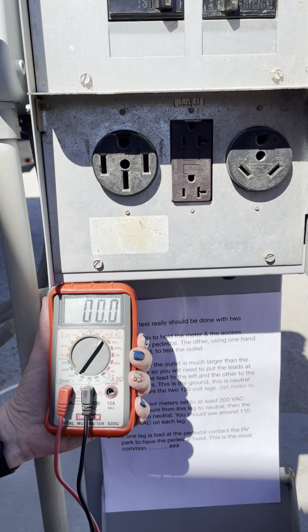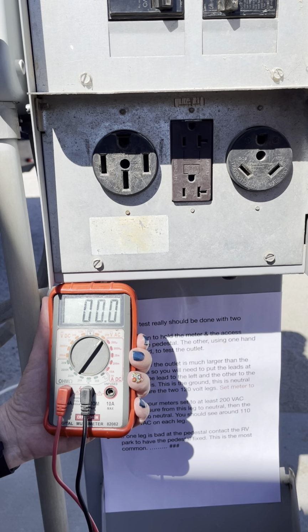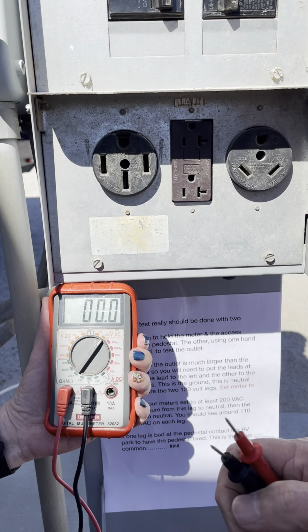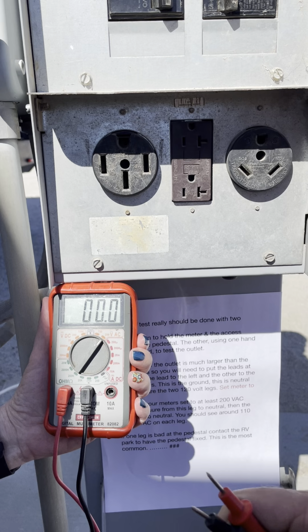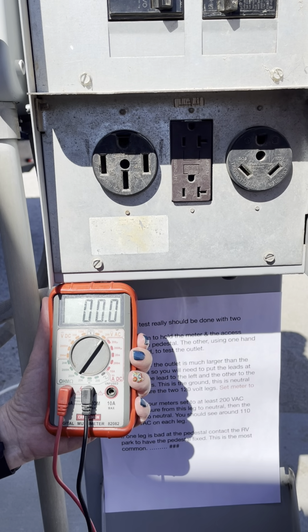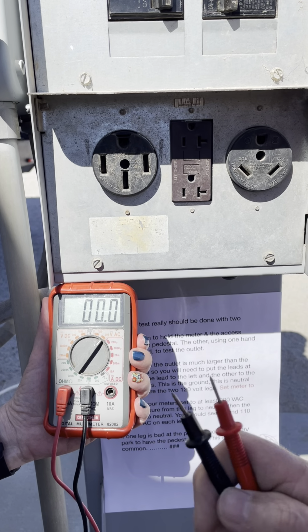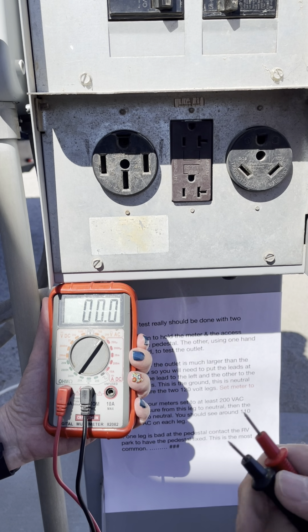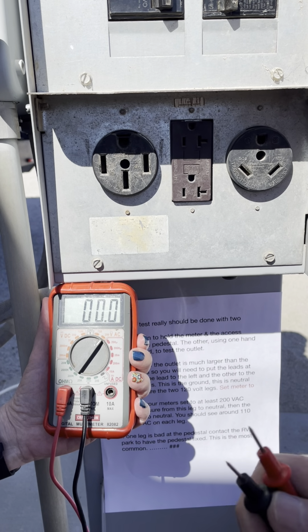This test really should be done with 2 people. One person to hold the meter and the access panel for the pedestal. In this case, for convenience, I've removed the access panel for the pedestal. Normally, you would not need to do that. The other person uses one hand for each lead to test the outlet. Now, the inside of the 50 amp outlet is much larger than my meter leads, and in my case, my meter leads won't reach.